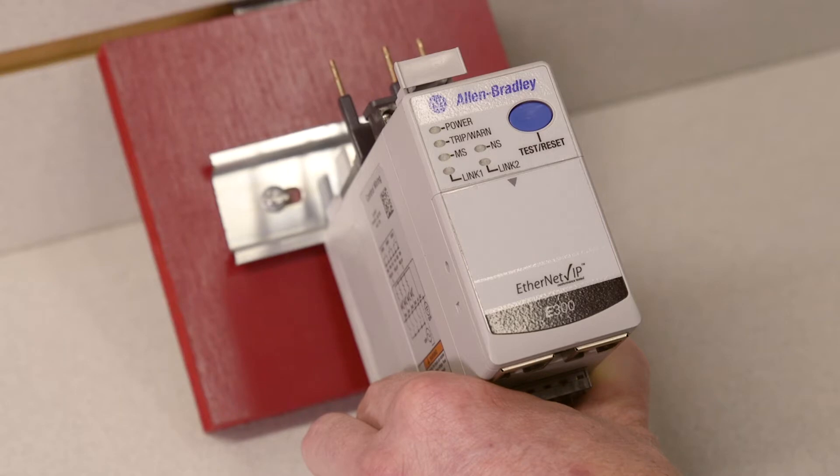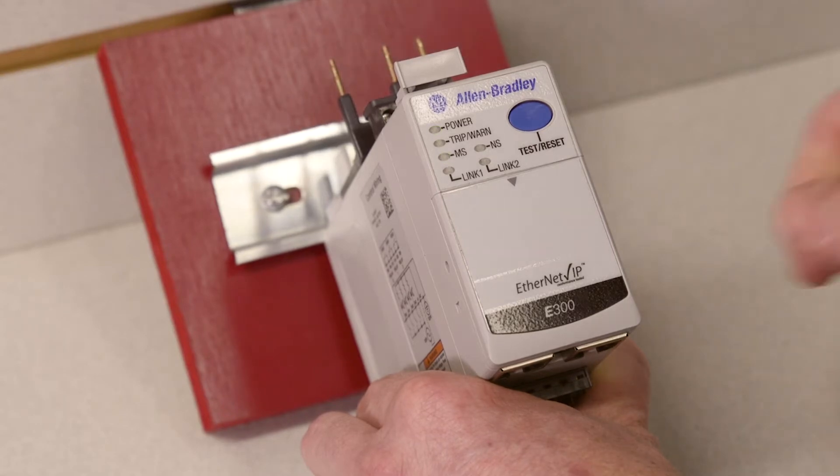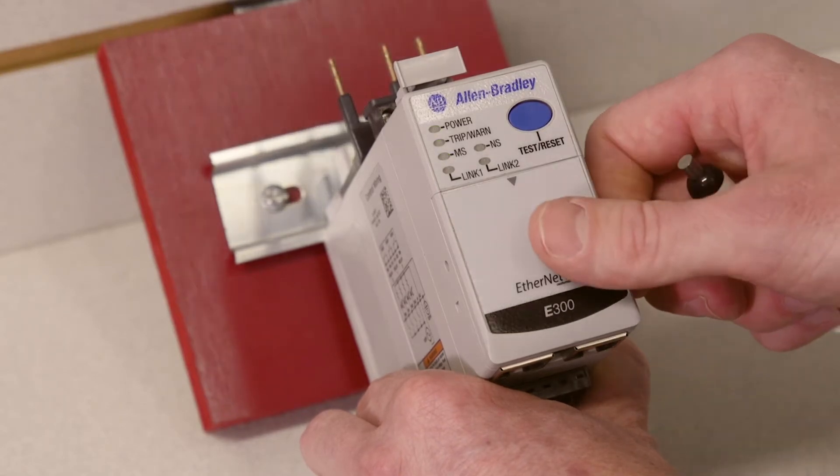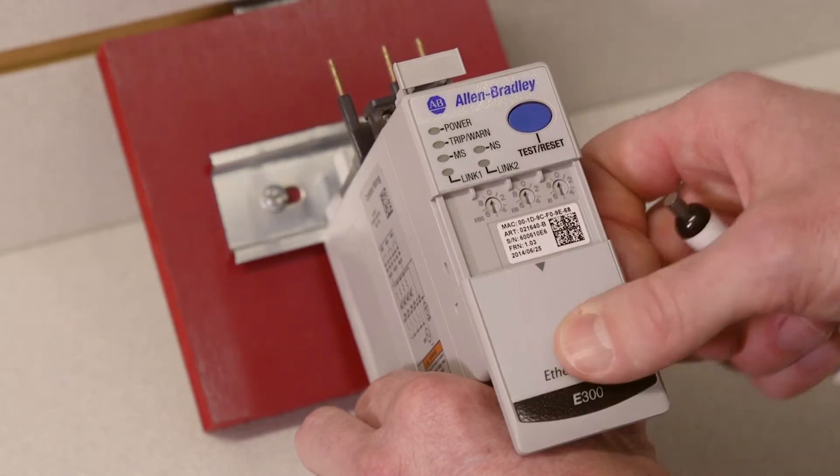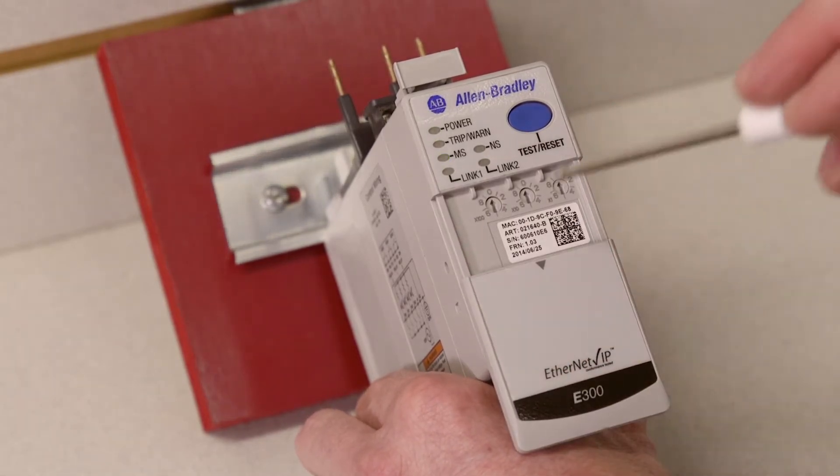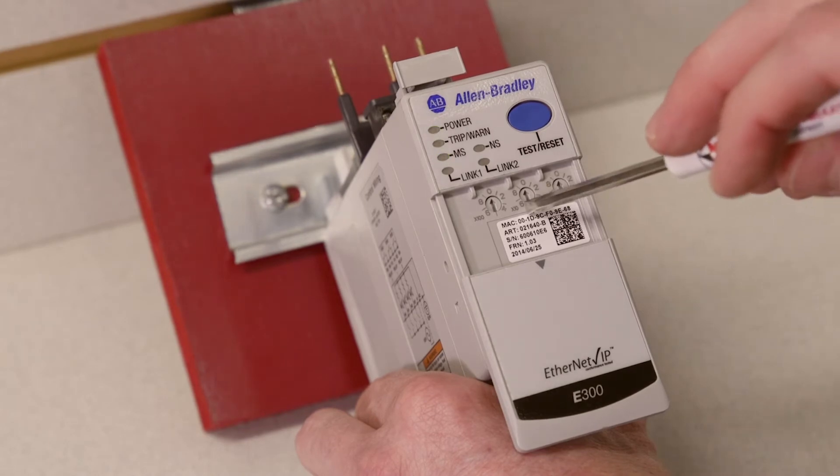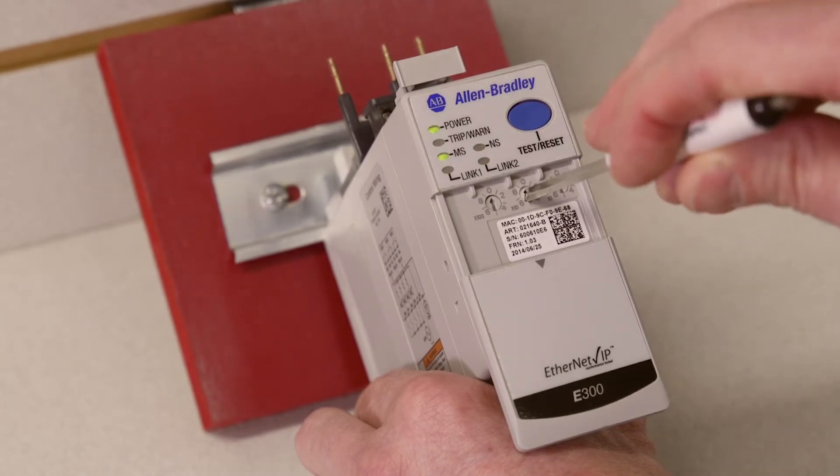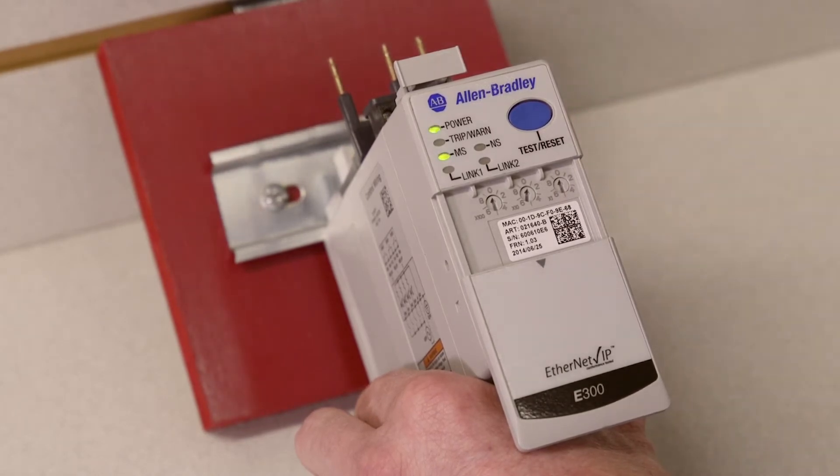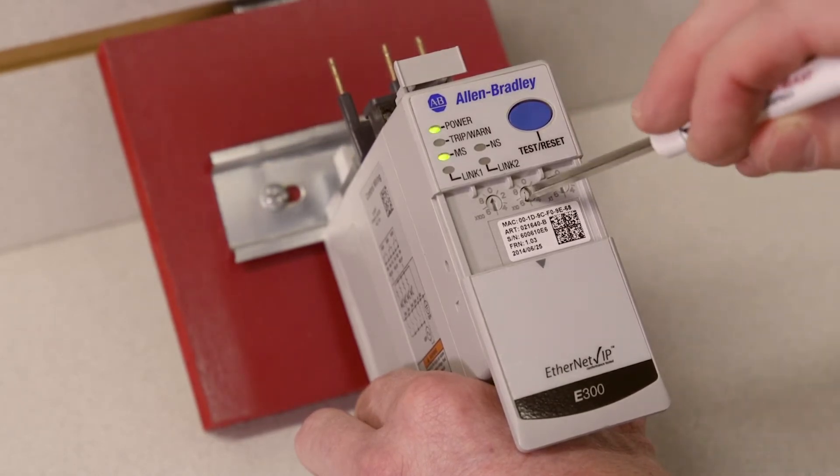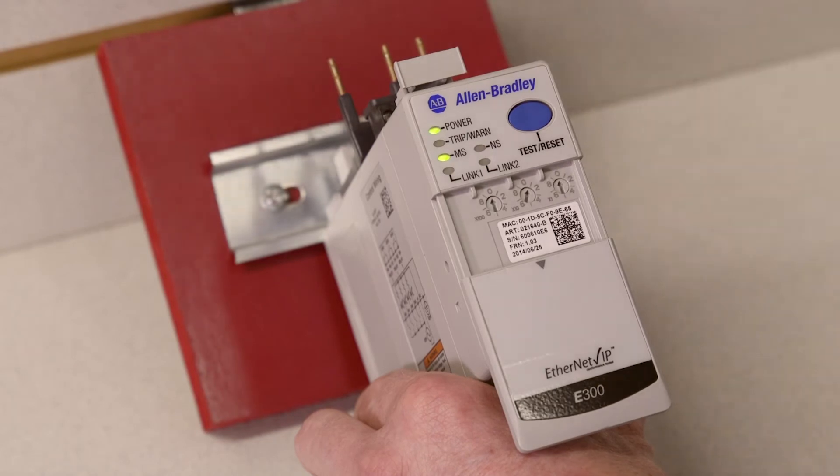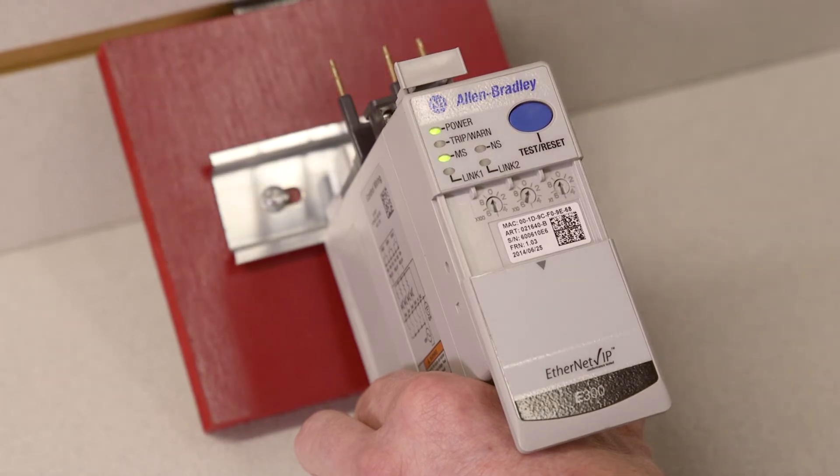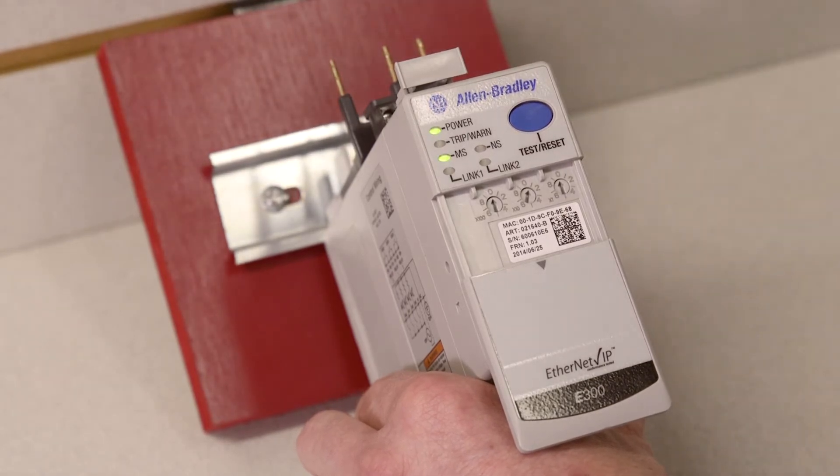Verify that the E300 is fully powered. Then turn the three dials of your selected IP address to 010, which I will use for this exercise. Once the dials are in place, cycle power to the E300.